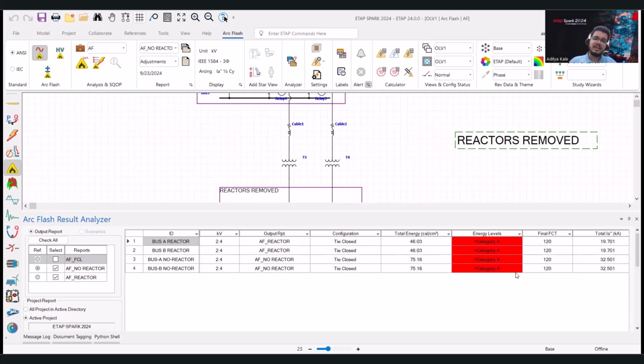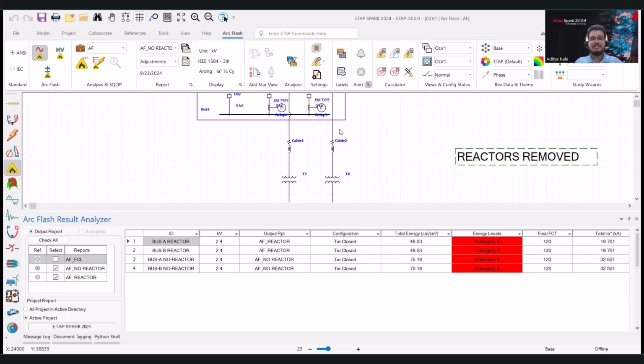The reason for this high incident arc flash energy is the upstream devices that we have, they are electromechanical type and they do not have advanced arc flash mitigating features, and nor do we have a 50 element enabled on these. So it takes a lot of time for these relays to acknowledge and clear the fault. Thus, we have to rely on the 2 second rule, so the fault gets cleared in 120 cycles. So we can see the energy is worsened when we take the reactor out.